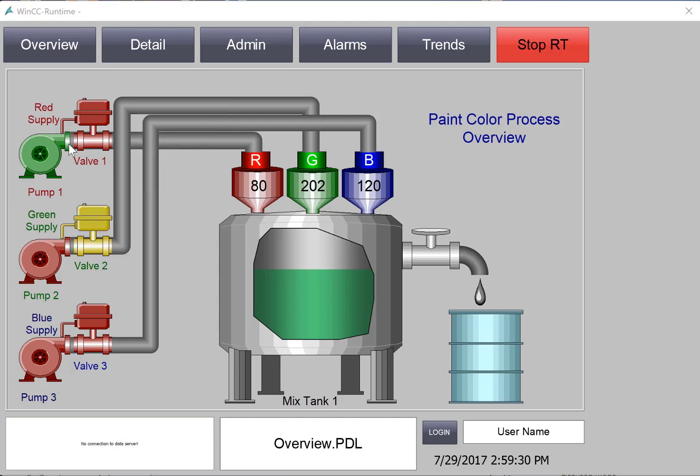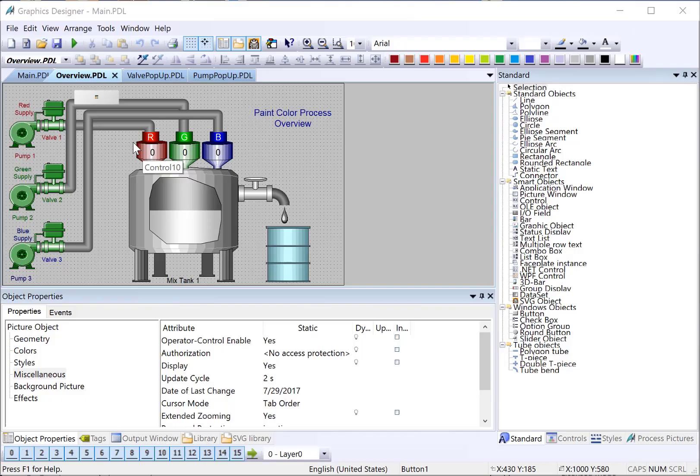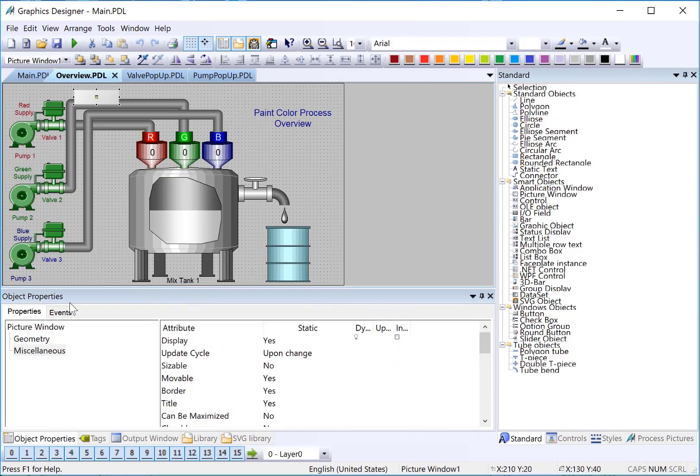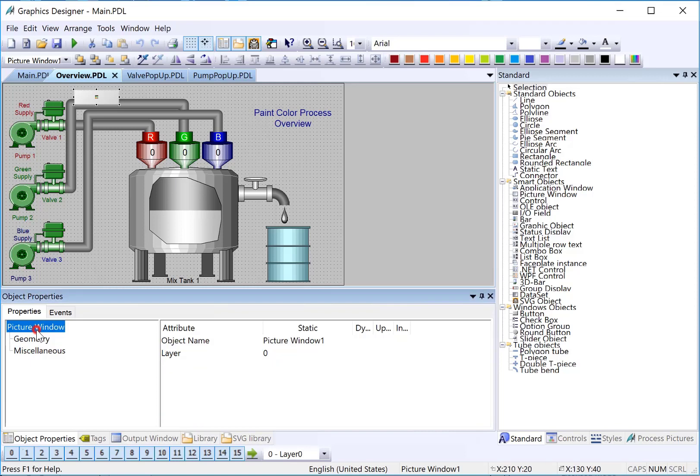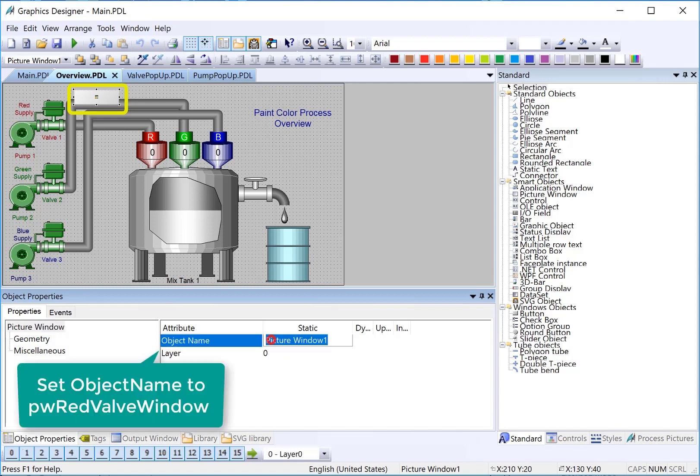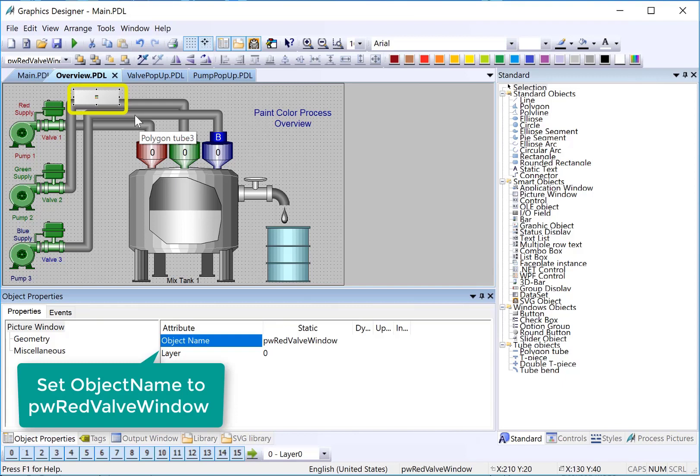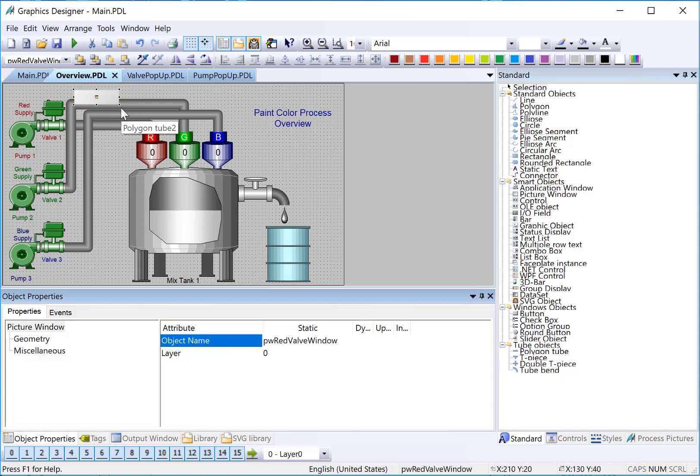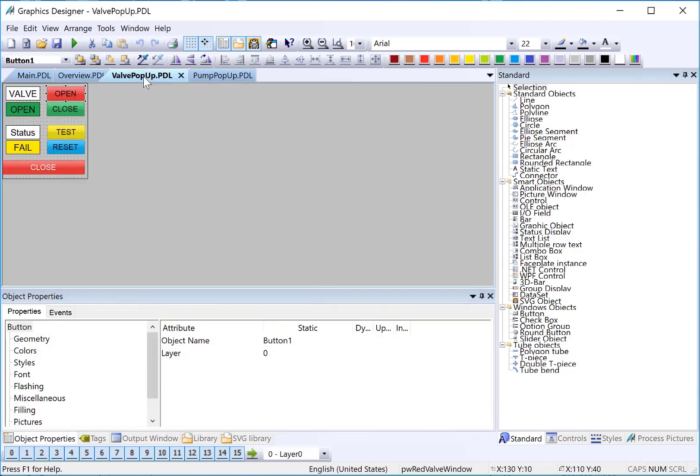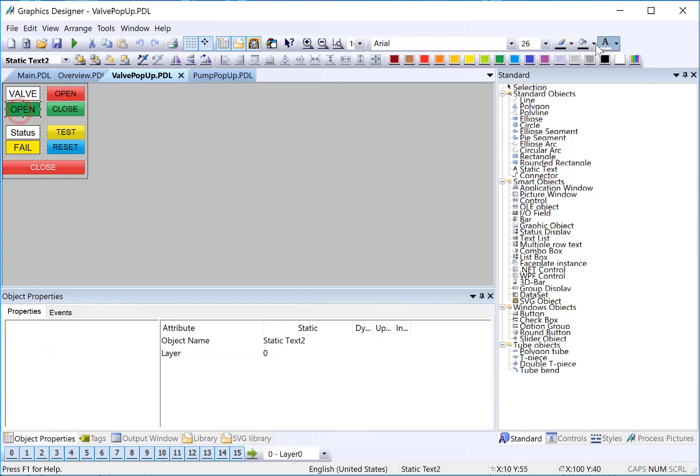Next we're going to duplicate that and we're going to make it so that when you click on the valve, we can call that pop-up. Because you notice that I don't have a way to get it back once I close it. So, we'll go back to our overview screen. We'll look at the name of this picture window. It's picture window one. We're going to change that because we're going to create six of these, one for each pump and valve. So, I will just call this PW for picture window, red valve window. I also noticed that we couldn't read the open and close labels very good. So, we're going to change the font to white. I'll go back to my valve pop-up here. And we'll just make it white. Hit save. We'll do the same thing on the pump.